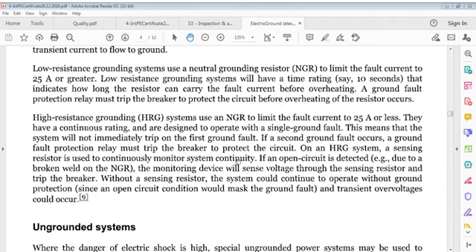High resistance ground. This was low resistance. Now we are saying a low resistance ground system shall have a time rating of 10 seconds, which indicates how long the resistor can carry fault current before overheating. A ground fault protection relay must trip the breaker to protect the circuit before overheating of the resistor occurs. Now, high resistance grounding.